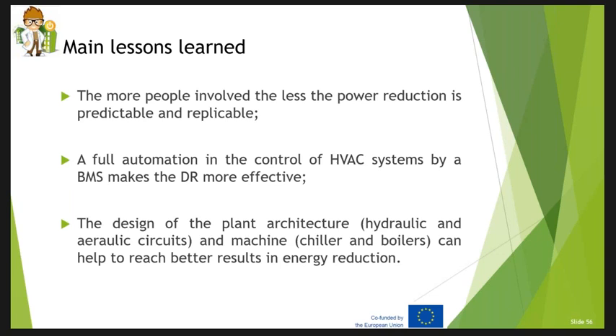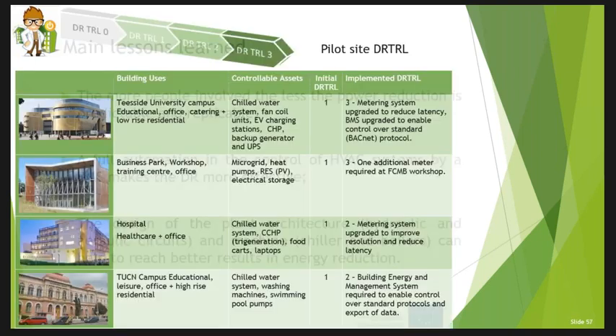Not always were we able to run scenarios like number 1 or number 4 with chillers involved, because we weren't able to change the settings of the machine as fast as we needed, also for the safety of operation of the machines and maintenance problems. So in the design of any new asset that we will install in the hospital, we will also think about the level of readiness for demand response. This last slide shows the implementation of demand response readiness, and thanks to the project we reached a partially automated level.